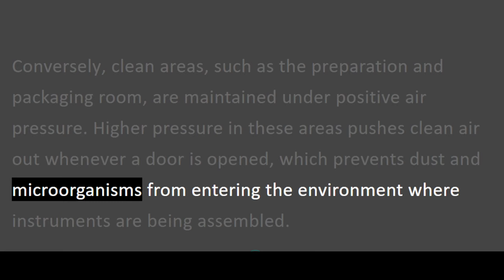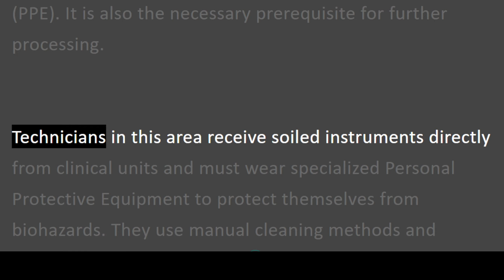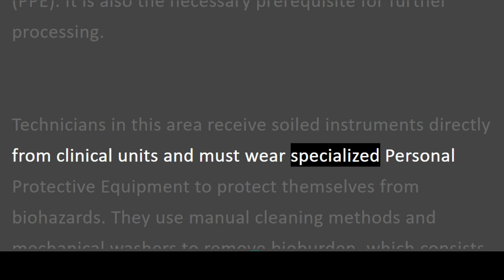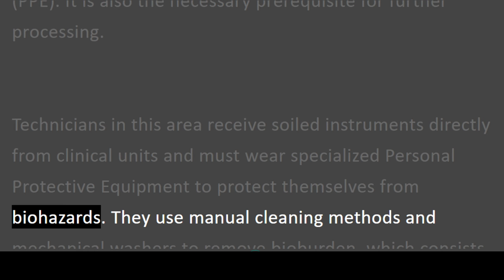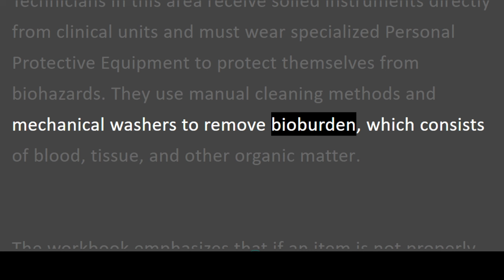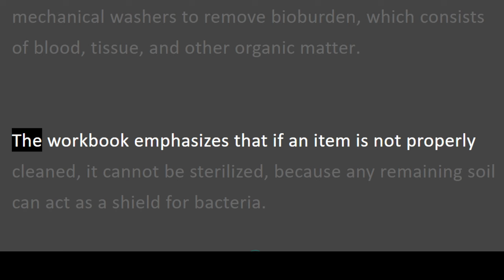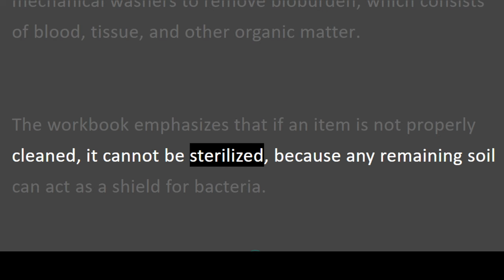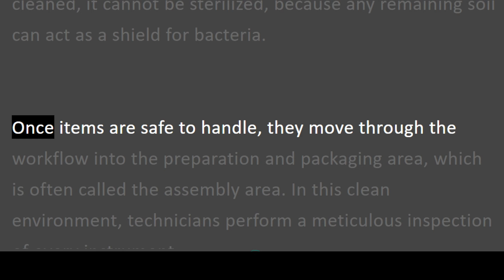The first and most critical step in the processing cycle is decontamination. This is the physical and chemical process of rendering an item safe for handling by personnel who are not wearing specialized personal protective equipment, PPE. It is also the necessary prerequisite for further processing. Technicians in this area receive soiled instruments directly from clinical units and must wear specialized personal protective equipment to protect themselves from biohazards. They use manual cleaning methods and mechanical washers to remove bioburden, which consists of blood, tissue, and other organic matter. The workbook emphasizes that if an item is not properly cleaned, it cannot be sterilized, because any remaining soil can act as a shield for bacteria.